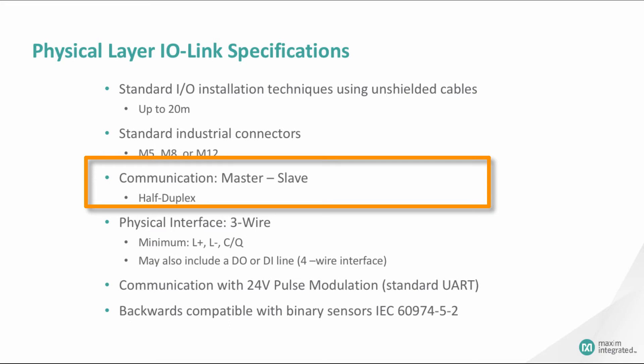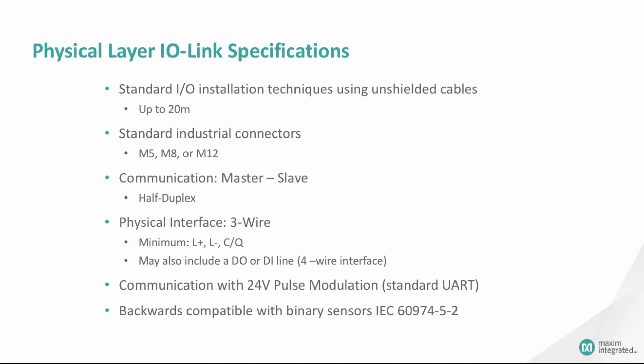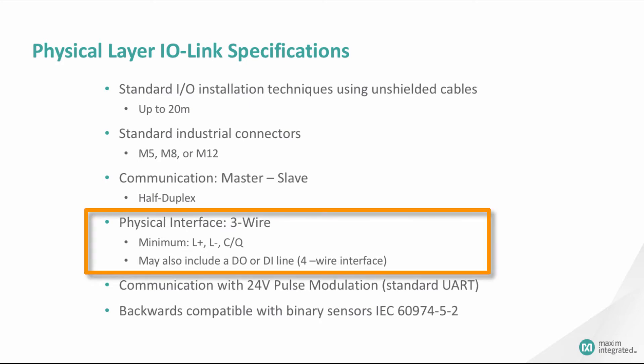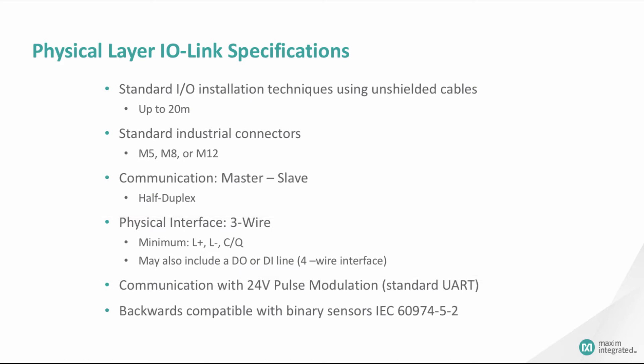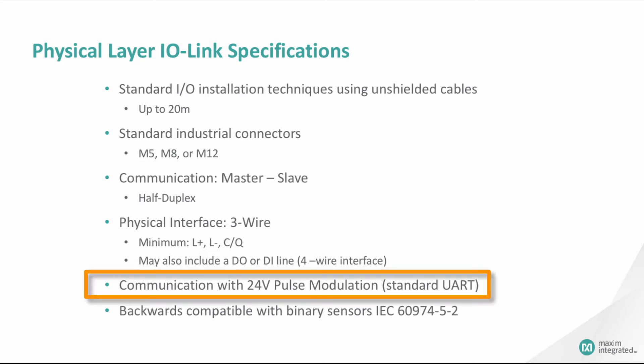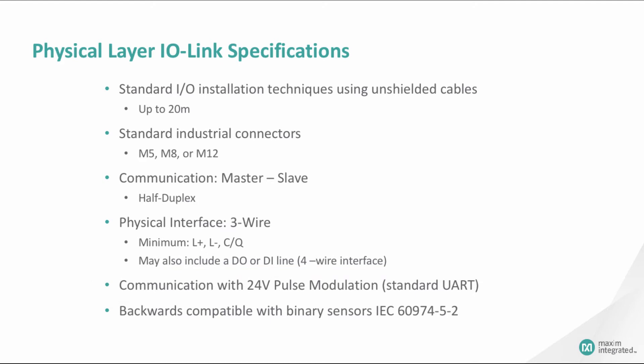IO-Link communication is between one master and one device — a sensor or actuator. Communication is binary and half-duplex. It requires a three-wire interface: supply, data, and ground. The supply range in an IO-Link system is 20 to 30 volts for the master, and 18 to 30 volts for the device. Communication is with 24-volt pulse modulation.